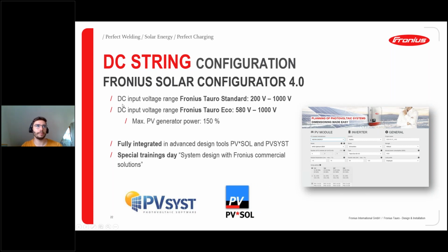Regarding the numbers, the DC input voltage range on the Fronius Tauro standard version with 3 MPP trackers is 200 to 1000 volts, and on the Fronius Tauro ECO 50 or 100 kW, it's 580 up to 1000 volts. So this 1000 volts is a limit we need to make sure not to exceed.